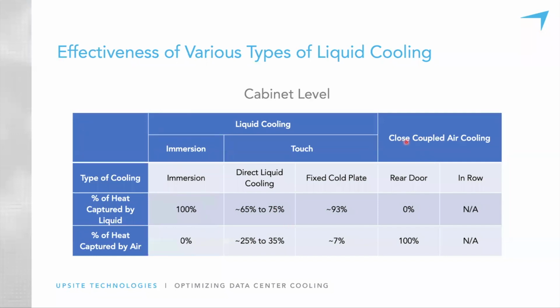So with the close coupled air cooling, rear door heat exchangers, and in-row cooling, none of the heat is picked up by liquid, not from the source. So those are not actually liquid cooled solutions. 100% of the heat is being picked up by air, and then it's giving that heat to the liquid.